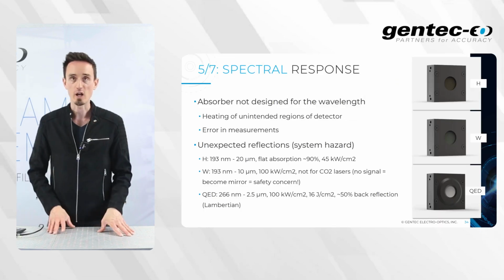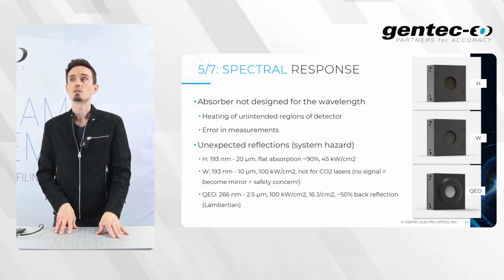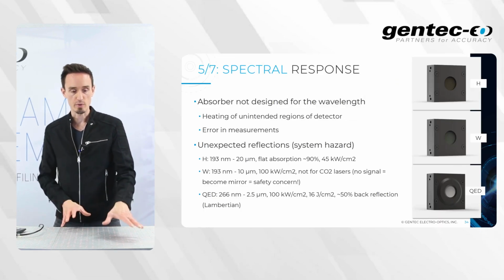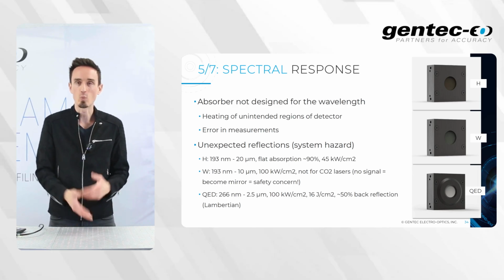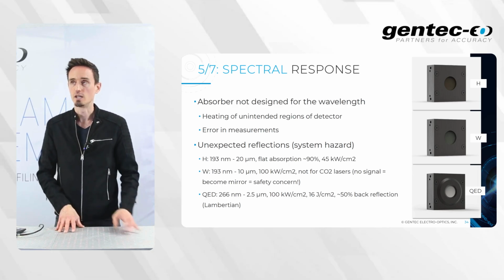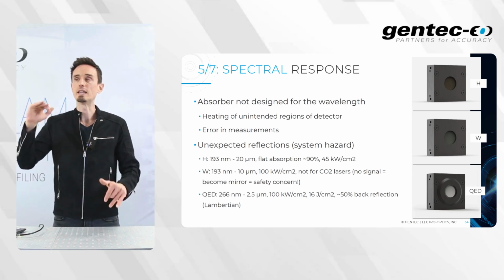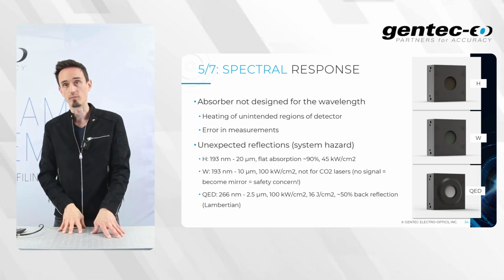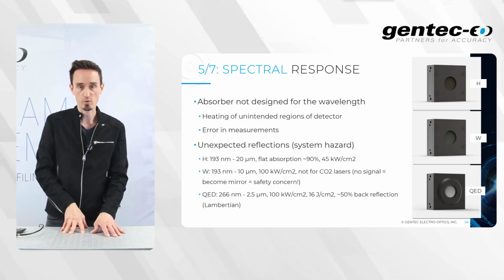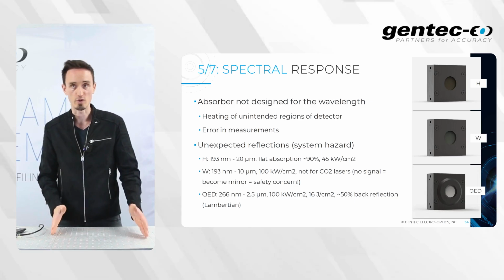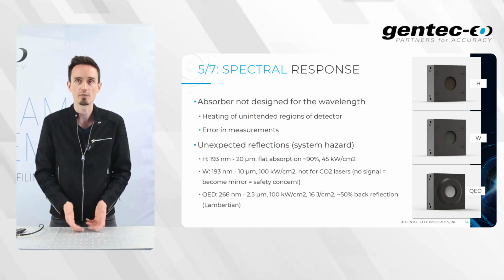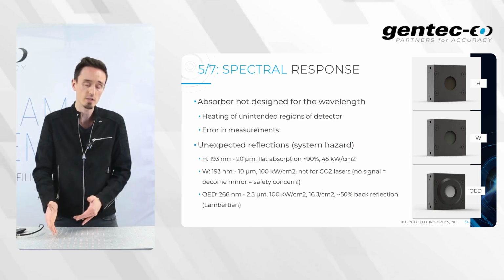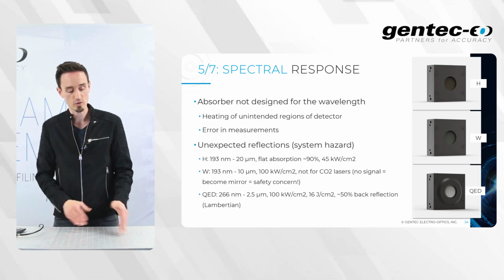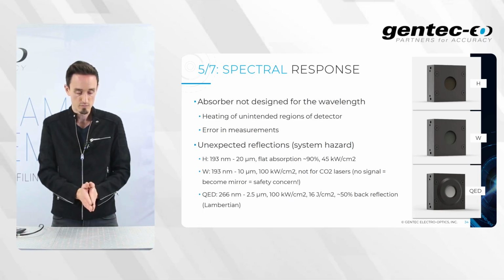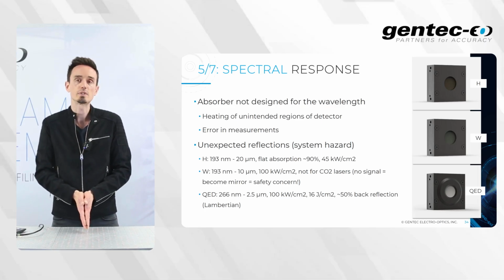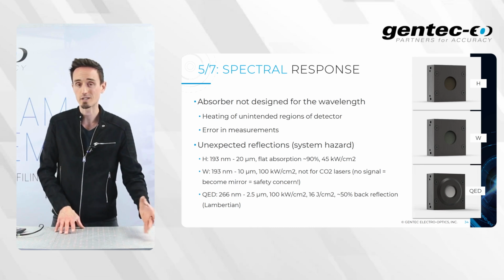About spectral response, the fifth one. So this is when the absorber is not necessarily designed for the wavelength of the laser here. I took three examples, the H, W, and QED. If you're not using the proper wavelength for which those absorbers are specified, that could result in some heating of unintended regions of the detector, potentially resulting in some damage in the end, and most of all, errors in measurements. But the main hazard here, potentially, is again about unexpected reflections.